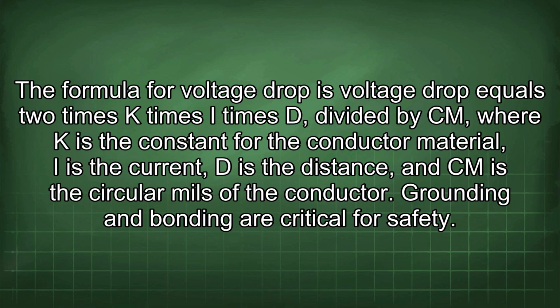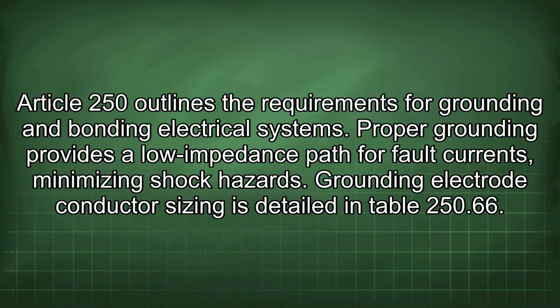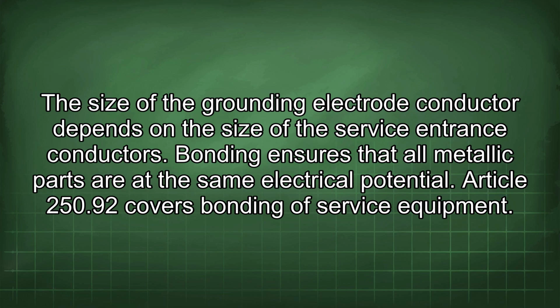Grounding and bonding are critical for safety. Article 250 outlines the requirements for grounding and bonding electrical systems. Proper grounding provides a low impedance path for fault currents, minimizing shock hazards. Grounding electrode conductor sizing is detailed in Table 250.66. The size of the grounding electrode conductor depends on the size of the service entrance conductors.